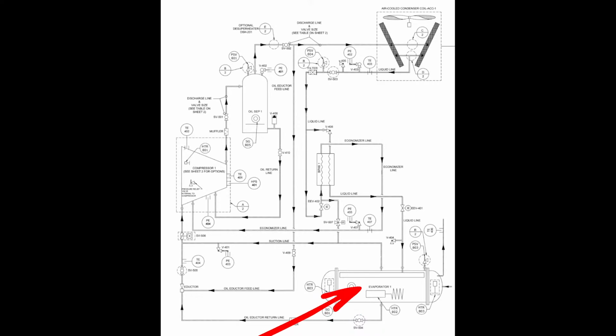Now, something else to note with these machines, these evaporators are separated. So they're run in series with each other between circuit 1 and circuit 2. So you're actually looking at what would be one circuit's evaporator, and then over here, there would be an independent evaporator for the other circuit, tied in series. So it flows into one circuit, flows through that heat exchanger into the other heat exchanger, and say all these are in a 2-pass configuration. So it makes 2 passes through, makes another 2 passes through, and then comes out the other evaporator. That's how these will be designed, and that's how you'll see them piped in the field.